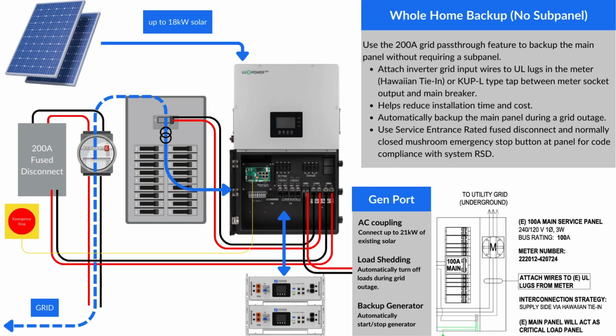Now, if you're also wondering, how do I do load shaving or load management in this setup if I don't have a sub panel? A common way of doing this is by using the generator port and triggering the smart loads feature of the inverter. And then you can move loads over here, like large air conditioners or even EV chargers, that you would want to be ordinarily turned off in a grid outage. And then by programming the inverter, that sub panel would automatically be de-energized in a grid outage.